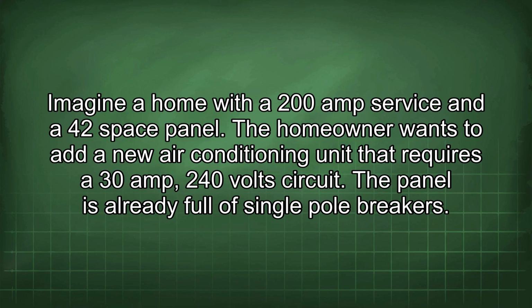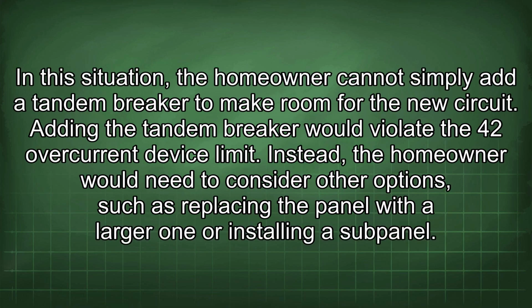The homeowner wants to add a new air conditioning unit that requires a 30 amp 240 volt circuit. The panel is already full of single pole breakers. In this situation, the homeowner cannot simply add a tandem breaker to make room for the new circuit. Adding the tandem breaker would violate the 42 overcurrent device limit.